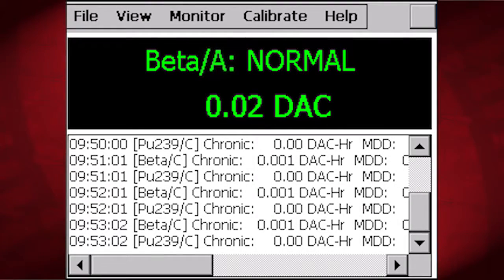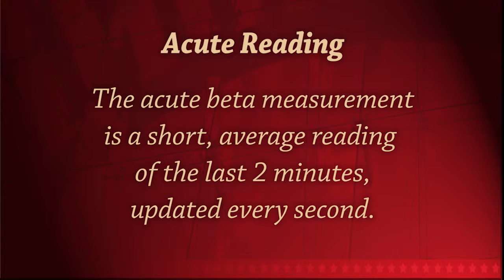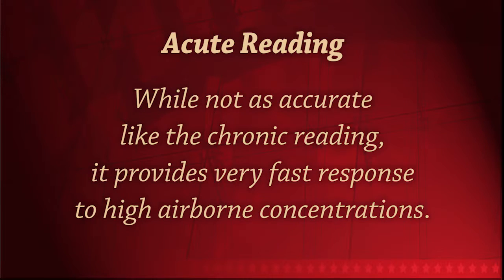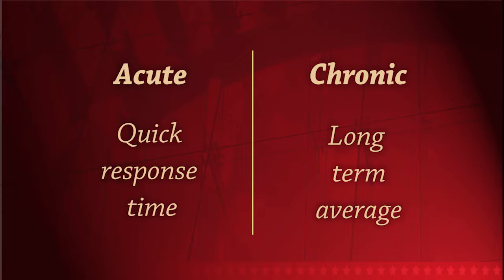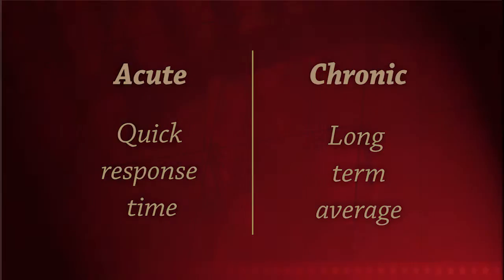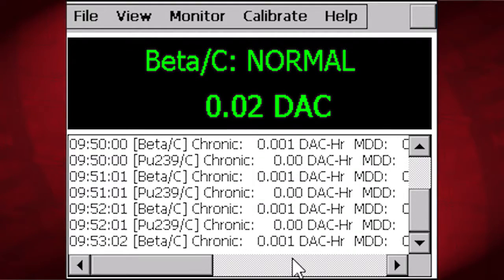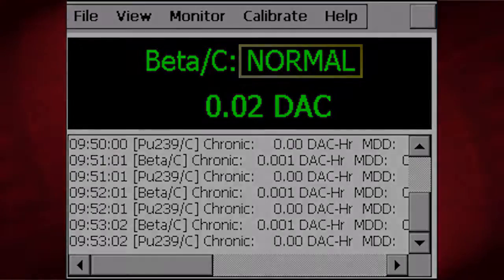every minute. The alternate measurement to the chronic reading is the acute reading, represented with a letter A. The acute beta measurement is a short average reading of the last 2 minutes, updated every second. While not as accurate as the chronic reading, it provides very fast response to high airborne concentrations. Think of the acute reading as a quick response time and the chronic as a long-term average. The status after the colon is normal, which indicates that everything is okay within the alarm limits.